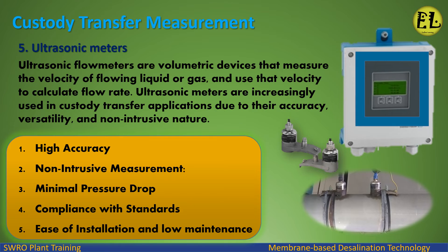Ultrasonic Flow Meters are volumetric devices that measure the velocity of flowing liquid or gas and use that velocity to calculate flow rate. Ultrasonic Meters are increasingly used in custody transfer applications due to their accuracy, versatility, and non-intrusive nature. Key advantages include high accuracy, non-intrusive measurement, minimal pressure drop, compliance with standards, and ease of installation and low maintenance.